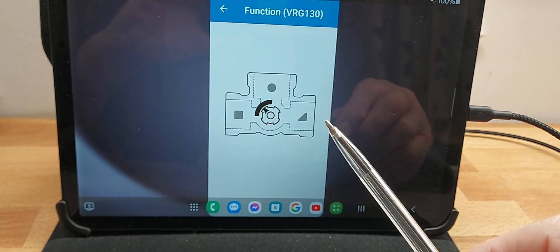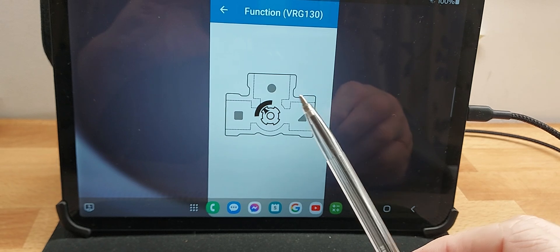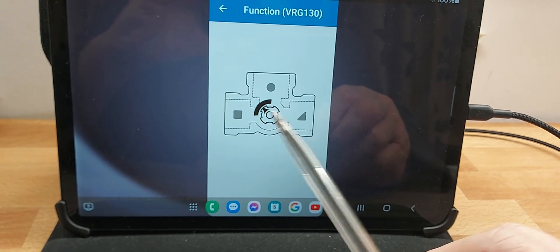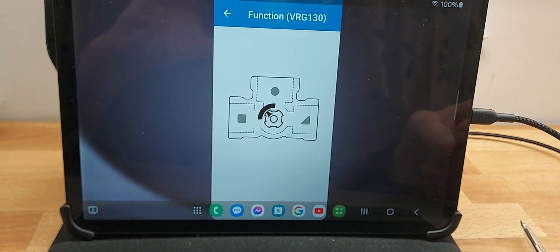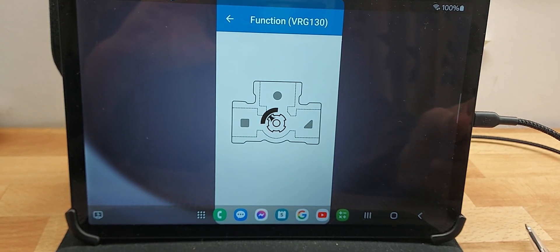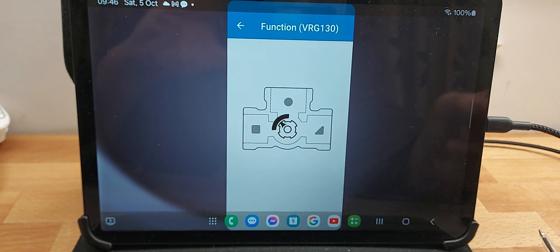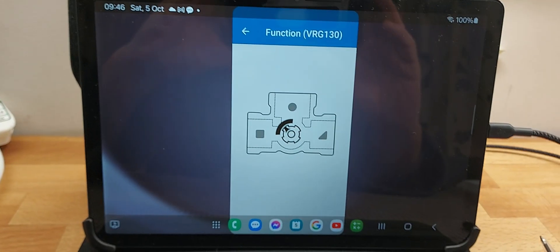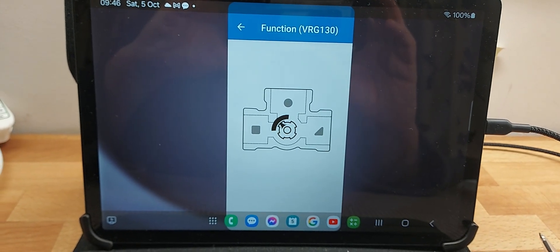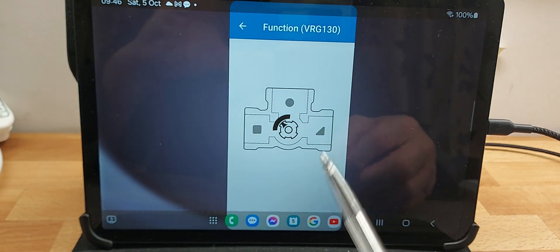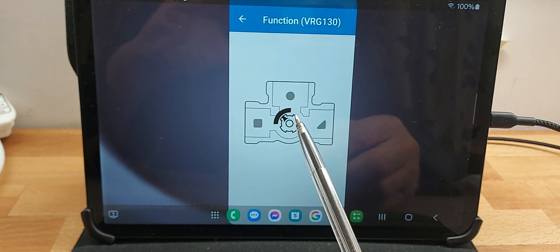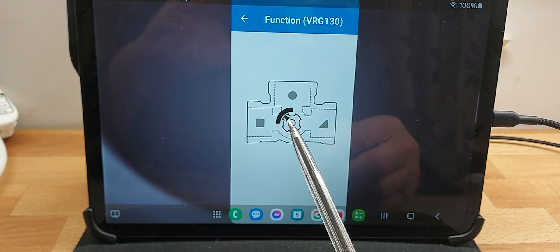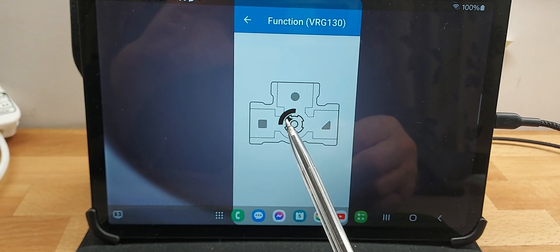We want that around 0.5, which is where the pressure loss is equal in the circuit we're providing and through the valve itself. When I was talking about commissioning these in the other video, I was talking about lining this up.